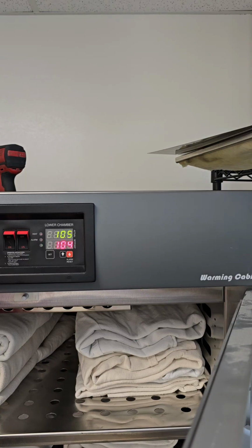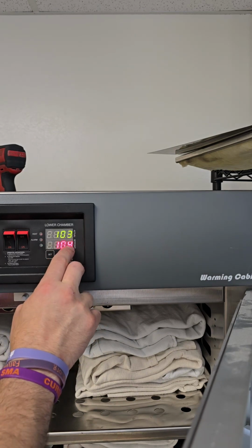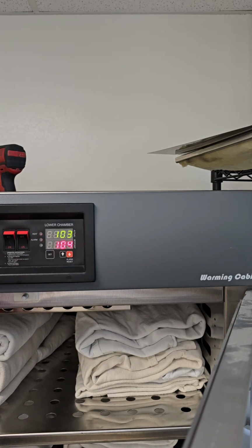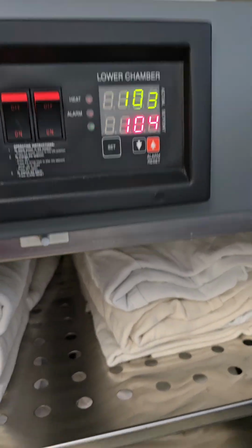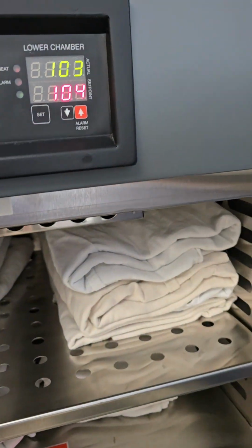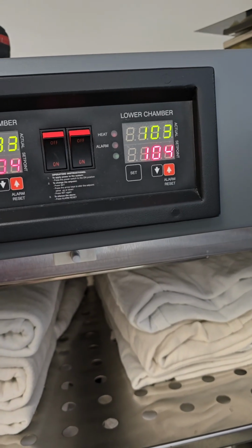Closer. 104, 105 up here. So I'm just going back and forth until, you know, when you're settled, your actual temperature and your thermometer line up. Also keep in mind your set point. It's going to be constantly trying to get there, so it'll be turning the heat on and off to get to that. So you want to try to be as close to that as you can when you're making these adjustments. I mean, right now, door open, but whatever, I'm 103, 3.5. 3.